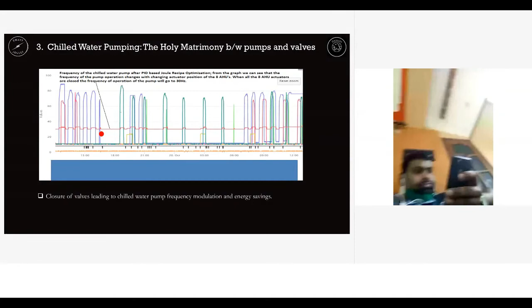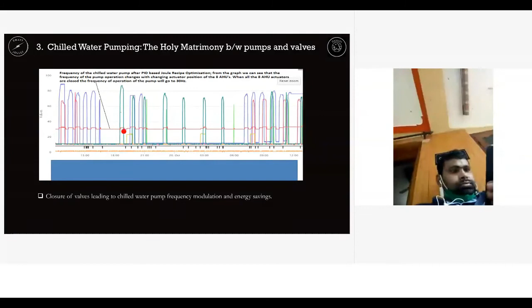So all these spikes that you see are actually the two-way valves opening and closing. There are around 20 two-way valves in this building that are under the BMS and IoT platform. When the area is operating, the valve opens, chilled water flows, and the space is air conditioned. When air conditioning is not needed, it switches down, and that happens for all the places. There are 20-some AHUs, and this is a span of 24 hours. The AHUs being turned on and turned off.